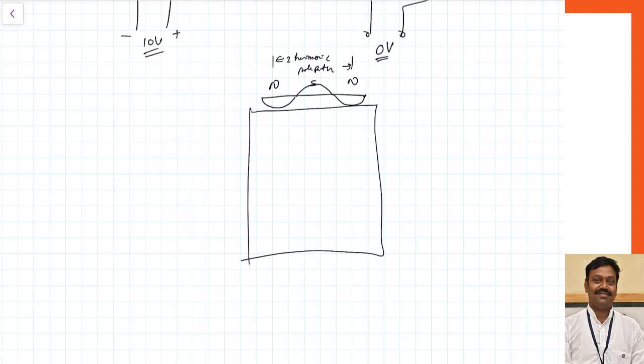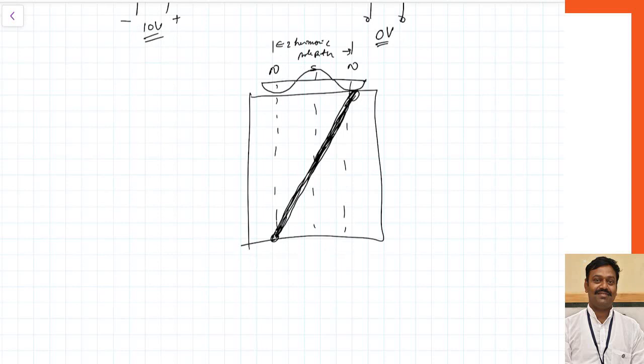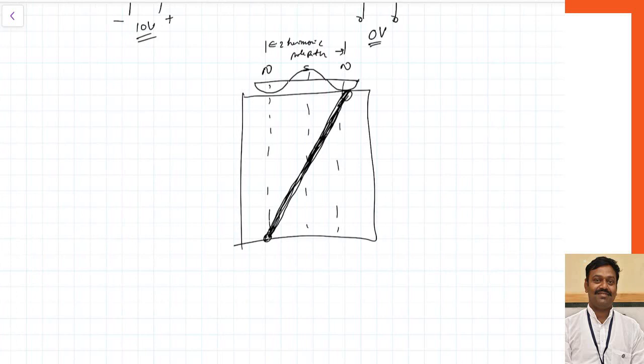If you want complete clarification of this, you can refer to my previous lecture where I explained slot harmonics and how the number of poles increases. Now what I will do: I will keep the rotor conductors in such a way that they start from one particular pole pitch and extend up to the next pole pitch. That means the rotor conductor will spread from a north pole to another north pole. The net EMF induced — you can see under the north pole EMF is one direction, under the south pole another direction, and again under the north pole another direction — so the net EMF induced will be equal to 0. So what we do is turn the conductor in such a direction that it covers two pole pitches, meaning we are shifting the conductor away from the parallel axis at some angle. This is called the skewing of the rotor slots. Because of the skewing of the rotor slots, the net EMF induced for that particular harmonic content can be made equal to 0. That is why skewing of the rotor slots is done.